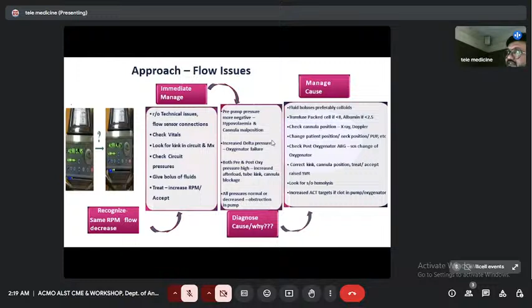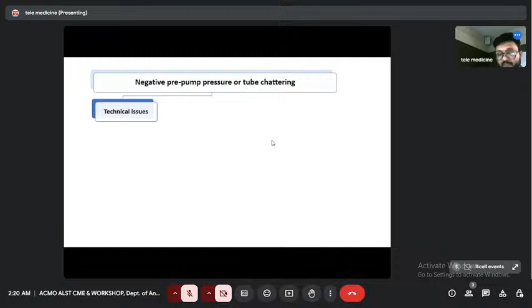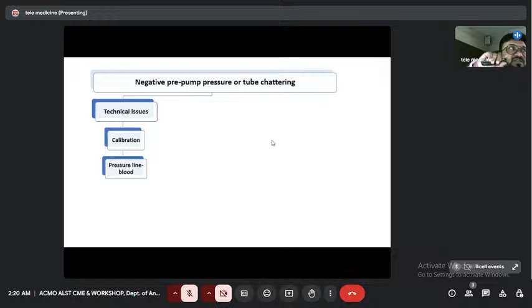If a negative pre-pump pressure is there, how to approach that patient? Like chattering is there in the tube and all, how to approach? First, you have to rule out the technical issues I told you already. So calibrate the pre-pressure line. If any blood clot is in the pressure lines, just remove that one. And after ruling out the technical issues, go for the patient-related causes. If a sudden negative pressure is caused because of a kinking in the circuit or kinking in the cannulas or cannula malposition, correct all these things.